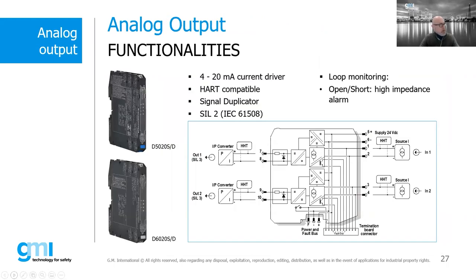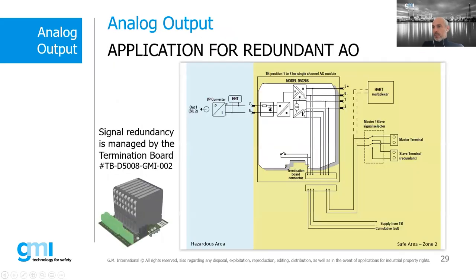For analog output, we similarly have modules with single or dual channels, compatible with HART protocol for transparent communication, and with the possibility of having loop monitoring for open circuit, short circuit, and high impedance alarms.